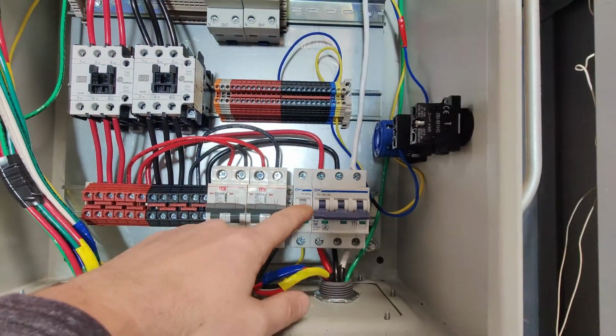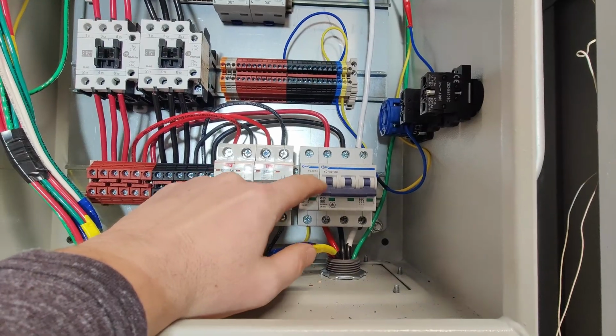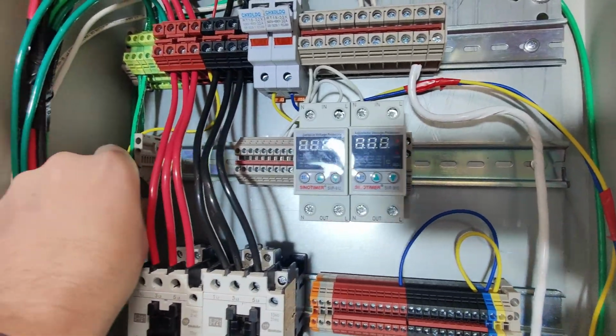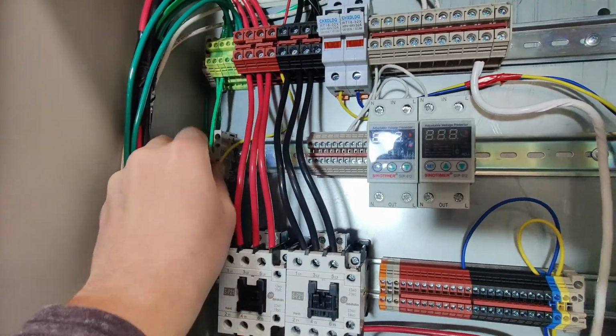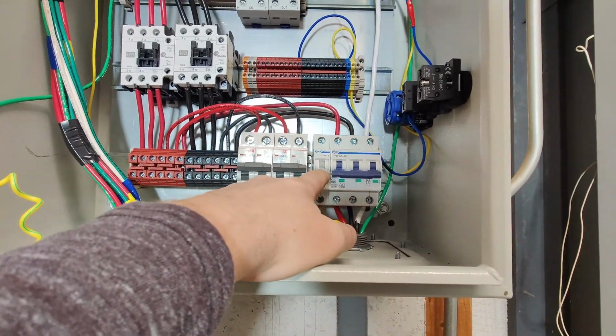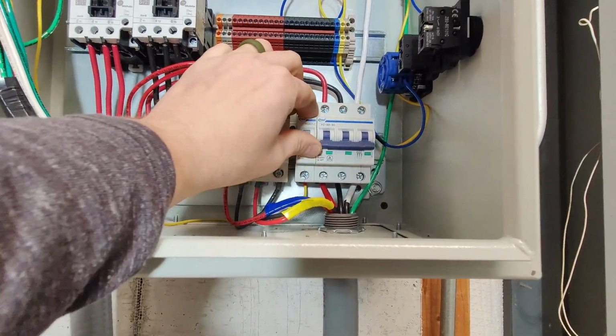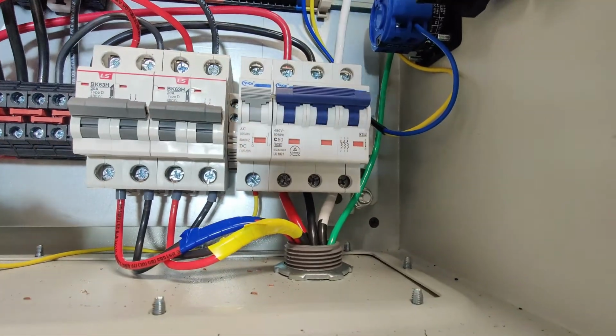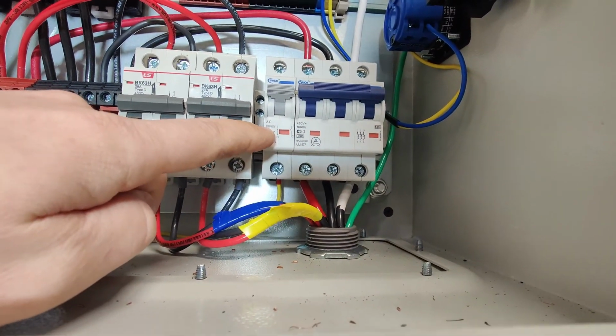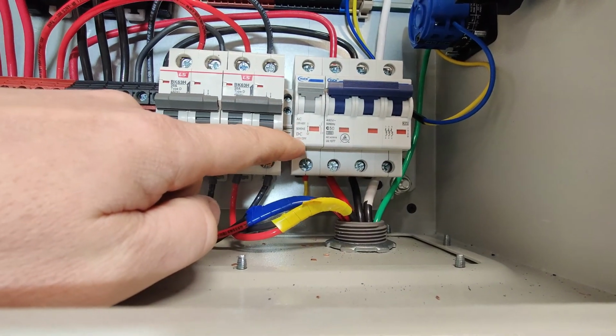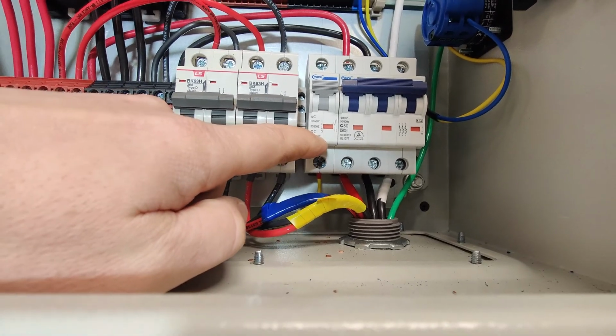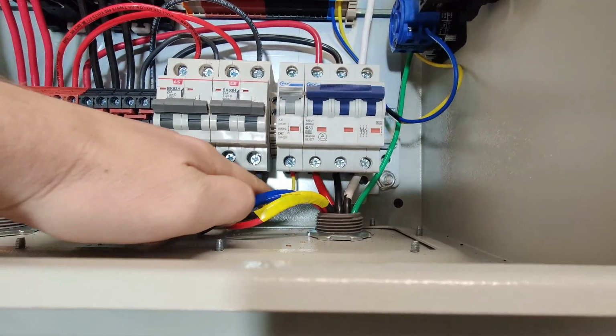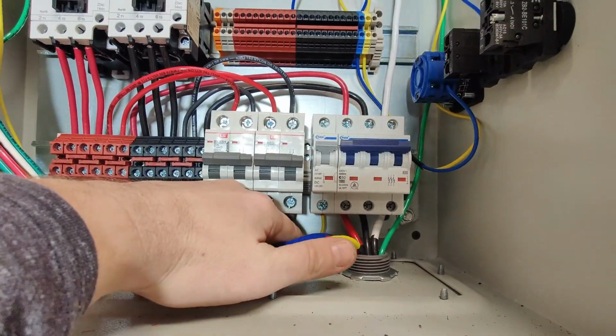If we have a fuse failure, our final fail-safe mechanism of activating the shunt trip won't happen if a fuse gets blown out. So what we want to have is this wire directly tied into our hot leg, and rely on the shunt trip itself, the protection circuitry inside of the shunt trip here, to function. So if you look at the shunt trip breaker, we can see that it will accept AC voltage from 110 volts to 400 volts, and it will accept a DC voltage 110 volts to 220 volts.